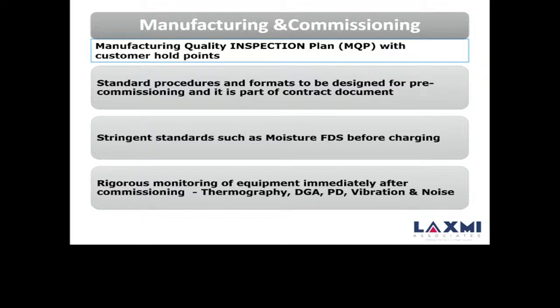Now, there are some suggestions here. During commissioning, first, the inspection plan at the factory should be very exclusive and detailed, with stage inspection and some customer hold points. If you really want a quality transformer, that is something that will add on. Then standard procedures and formats to record the data once it arrives at site. Utilities have them, but not all utilities do. So if you have your own standards and procedures with benchmarking of the data you accept when you receive at site, it is very good to have as a procedure and standard.